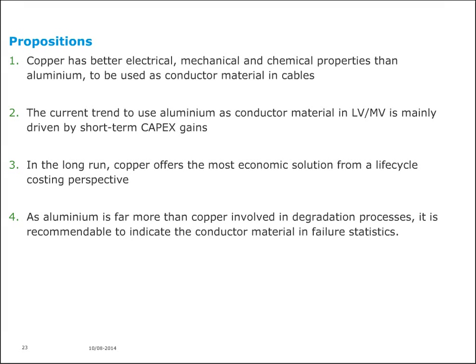Now proposition number 2: the current trend to use aluminum as conductor material in low voltage and medium voltage cables is mainly driven by short-term capex gains. Maybe you remember what I quoted from the BICC handbook - they said exactly the same, that aluminum is mostly selected because of cost. This is a short-term capex view.